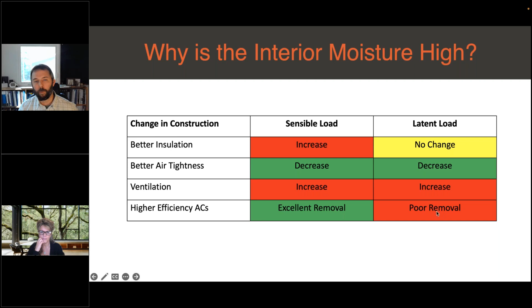As we add ventilation back in because of this better air tightness, it's a balancing act—we're increasing both the sensible load and the latent load. And with higher efficiency ACs, we get excellent sensible removal, but typically poor latent performance.